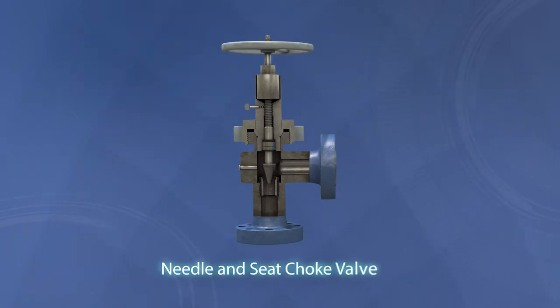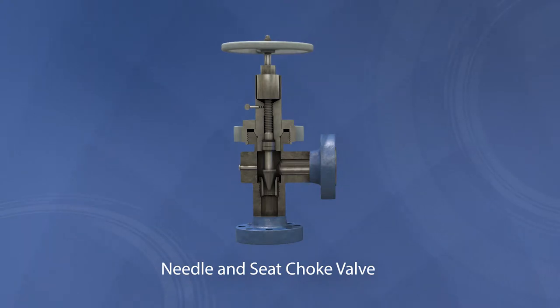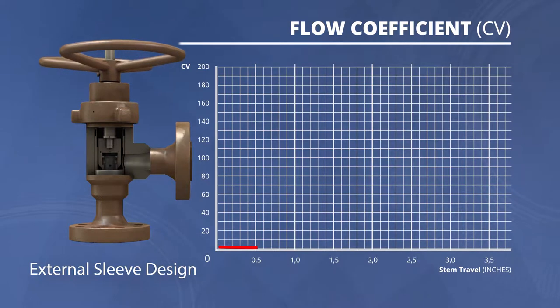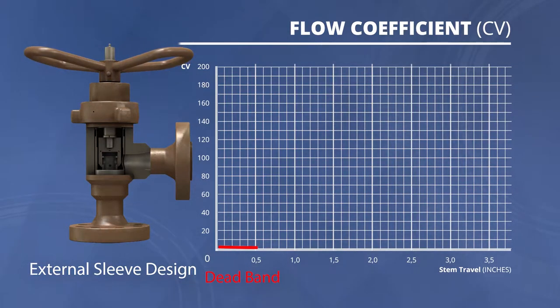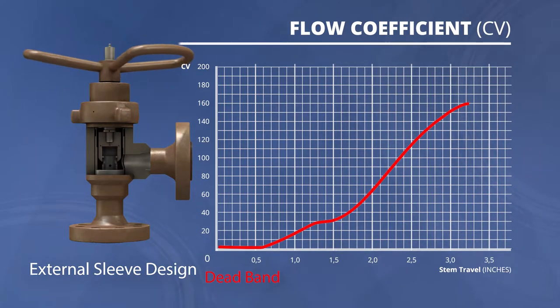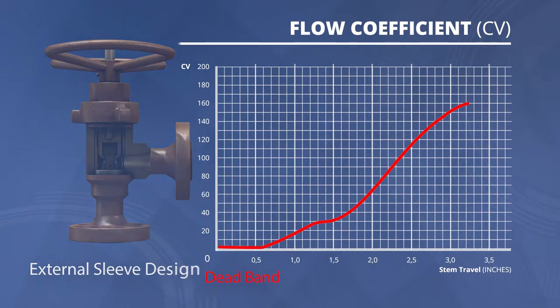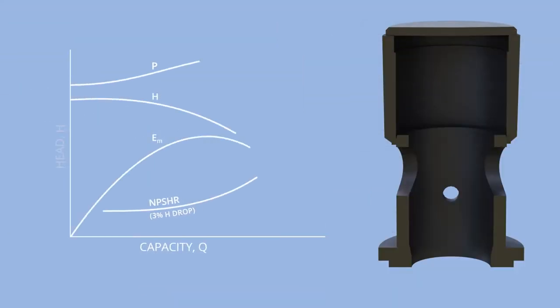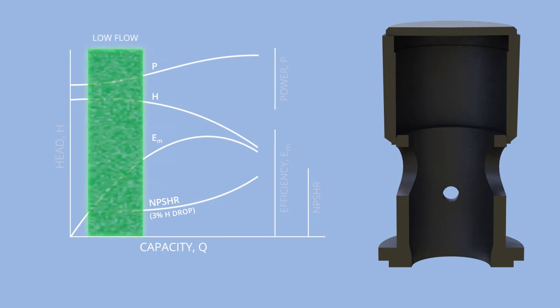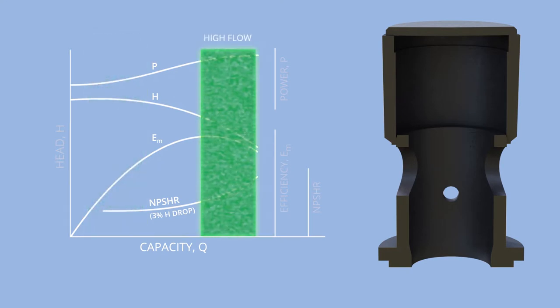When the seating area is close to the throttling area, erosion issues may occur, as frequently happens with the needle and seat valve. MasterFLOW solved this issue by incorporating a dead band area in the design of the external sleeve and cage choke valve. The dead band ensures that the throttling area is far from the seat, resulting in an area of zero flow. MasterFLOW's custom trims can be designed for a specific pump curve, providing high loss coefficients at low flows and low loss coefficients at high flows.